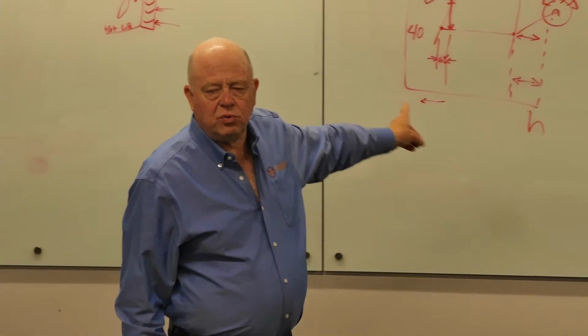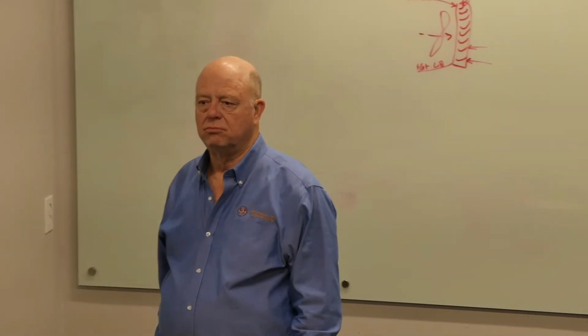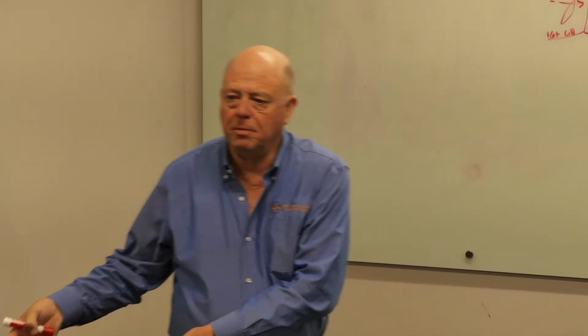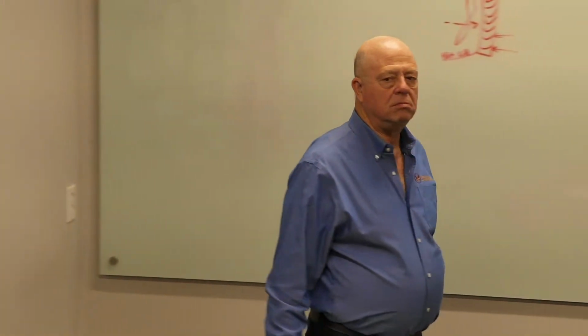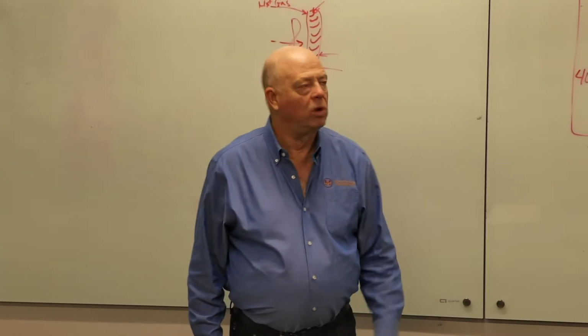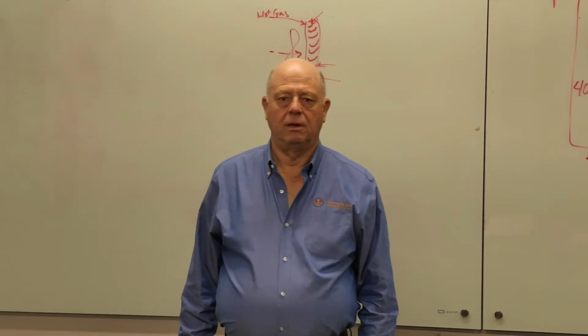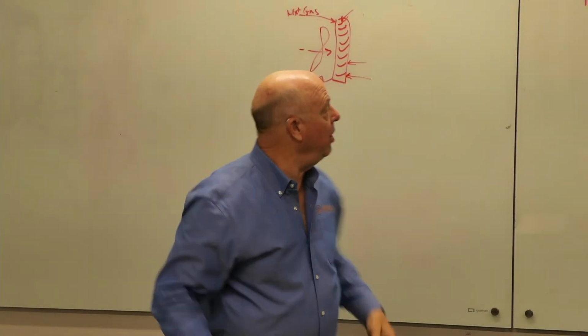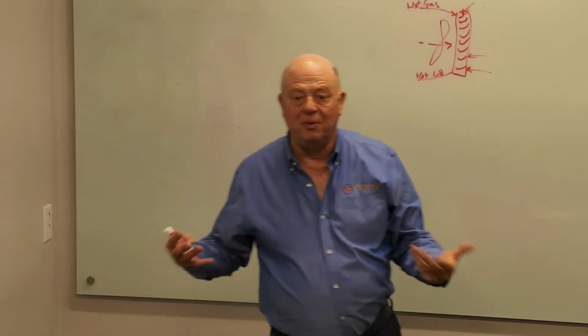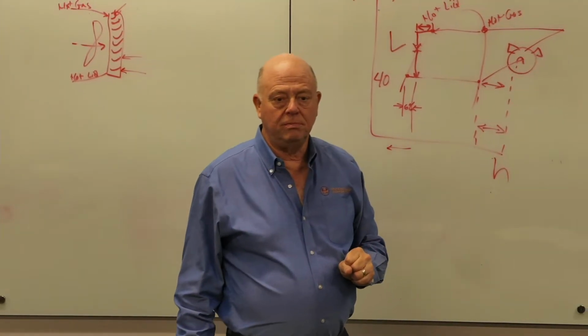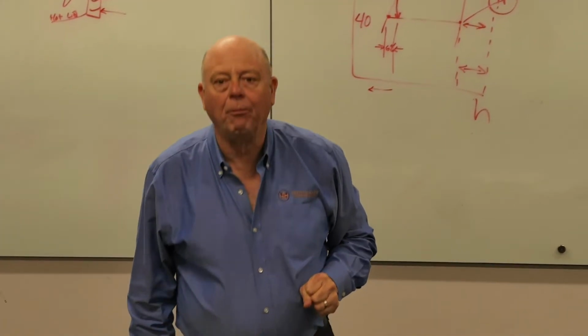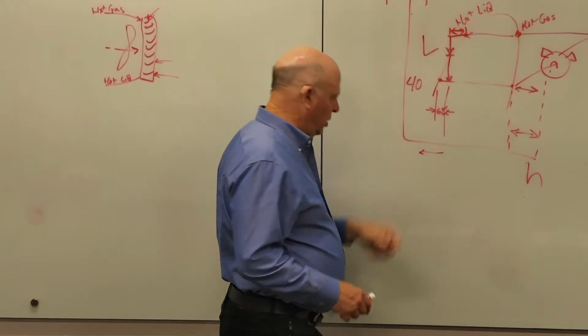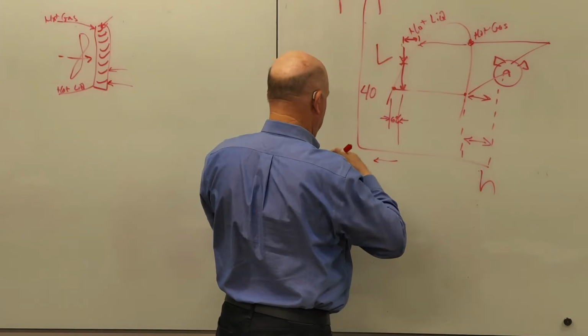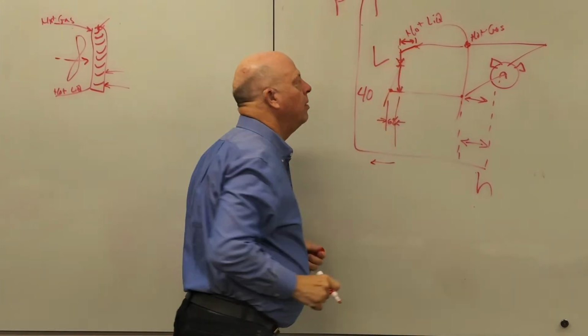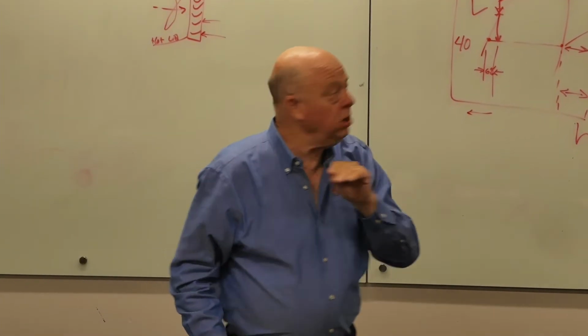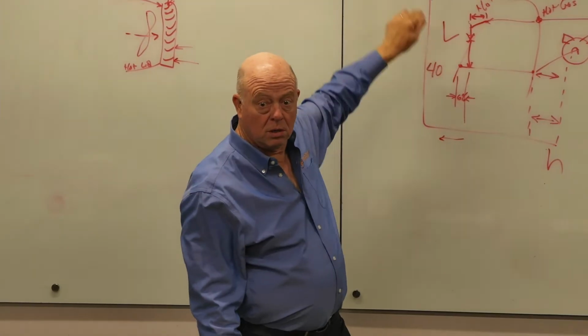So imagine that this is running. It's in the winter, because there's some cooling load that needs to be done in the building. And it's 55 degrees outside. What's that subcooling going to turn into? A lot of subcooling, right? Because now we've got 55-degree air and we're going to be removing it. So the question is, can you have too much subcooling? Yeah, you can. Because as this is getting cooler, it's not horizontal anymore. It's doing this. Because remember, temperature and pressure are linked. So as it gets cooler, the pressure's going down.